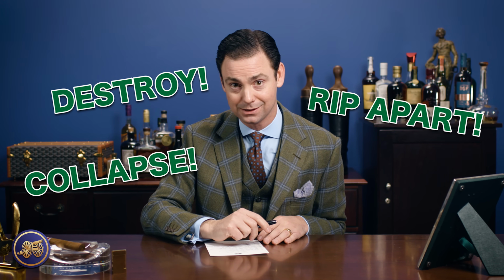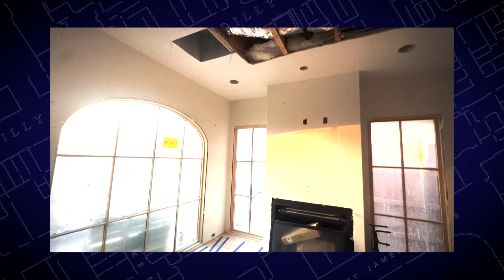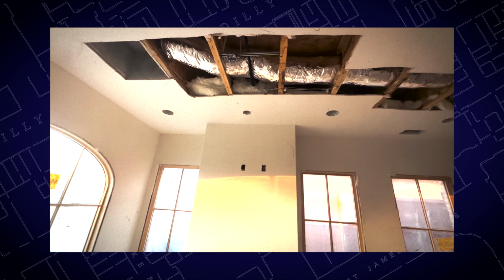So it turns out flex duct is only rated to 350 cubic feet a minute, which was not good because we had already installed the flex duct and sheetrocked over it. That meant if we tried to use the Cam Cleaner, it would destroy the ductwork, rip it apart, collapse it, and the system would fail. Long story short, it became clear we were going to have to tear out the sheetrock and replace that flex duct with hard, galvanized ductwork.